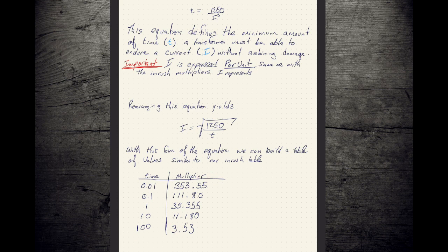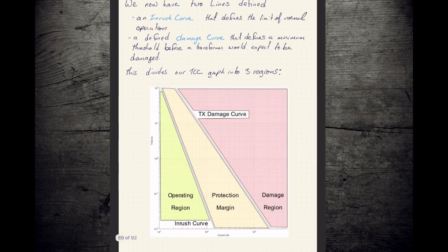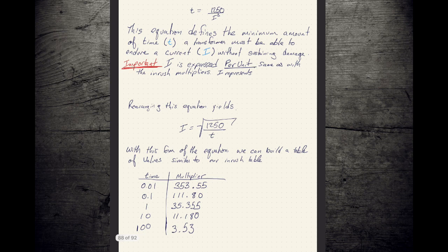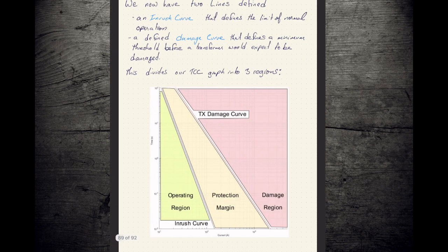If you really don't like math, as long as you use these times, you always end up with these multipliers. So pick your poison. You can calculate them on demand, or you can memorize this set, and it'll be enough to keep you rolling through this course. So what we can do is take our full load amps, multiply it out, and what we end up with is really two sets of lines. We end up with a line that is our inrush curve.